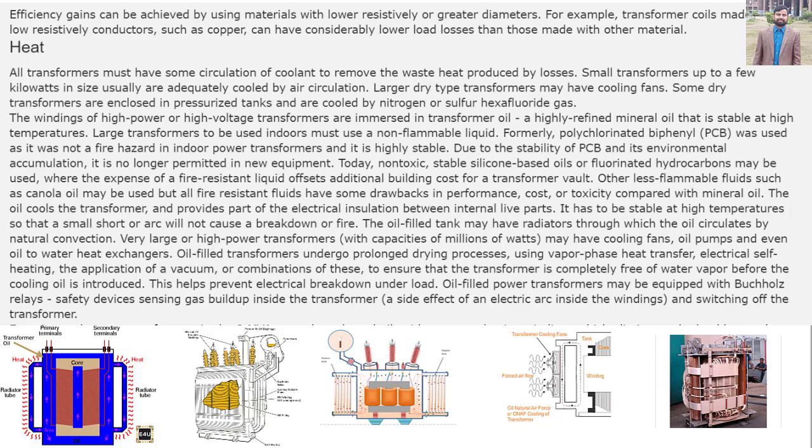This helps prevent electrical breakdown under load. Oil-filled power transformers may be equipped with Buchholz relays, safety devices sensing gas buildup inside the transformer, a side effect of an electric arc inside the windings, and switching off the transformer.